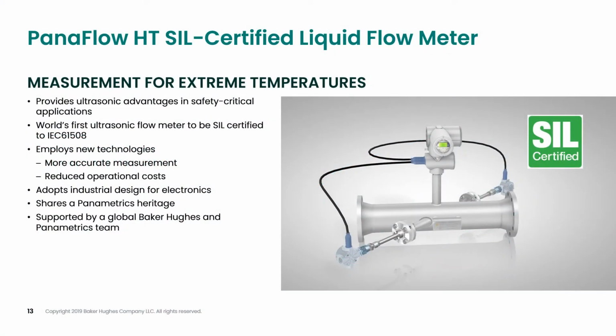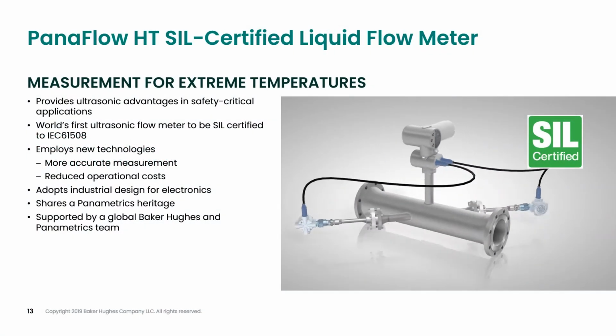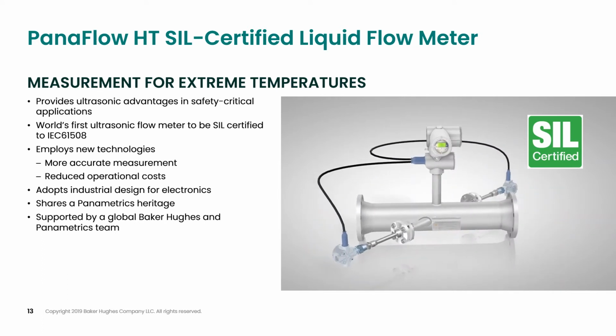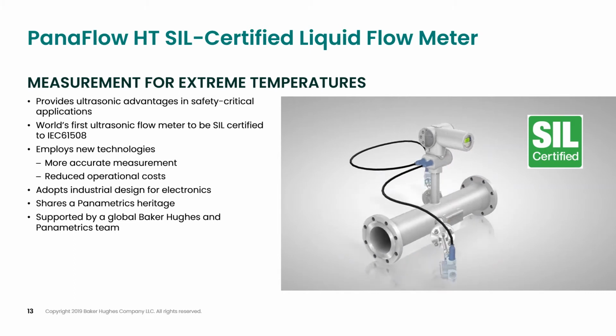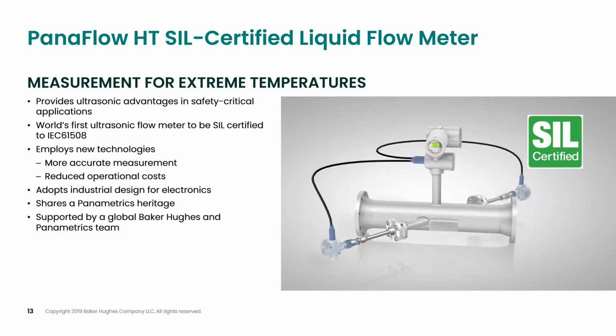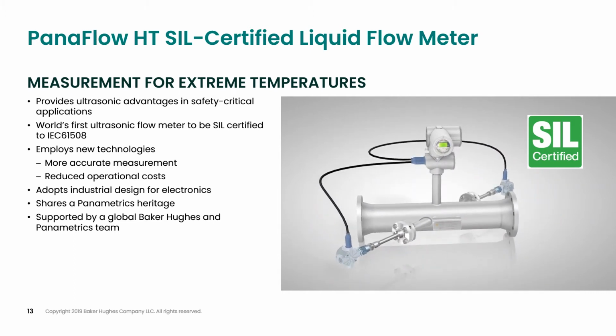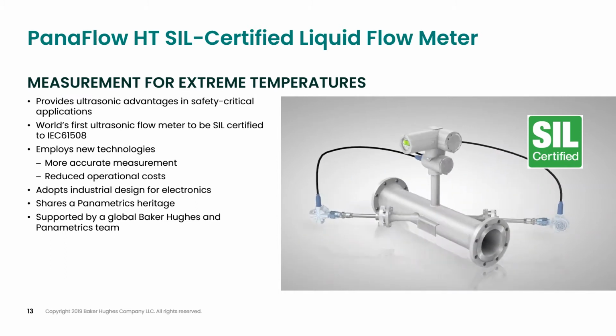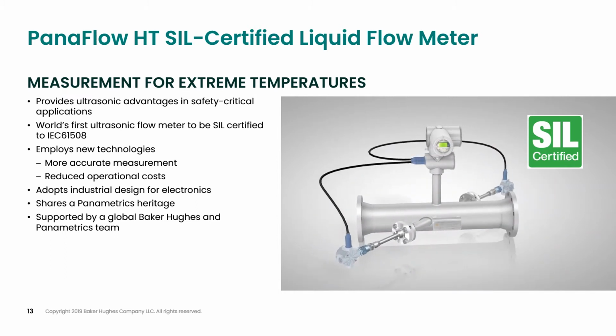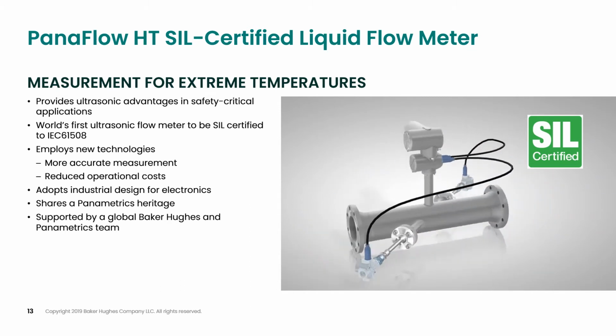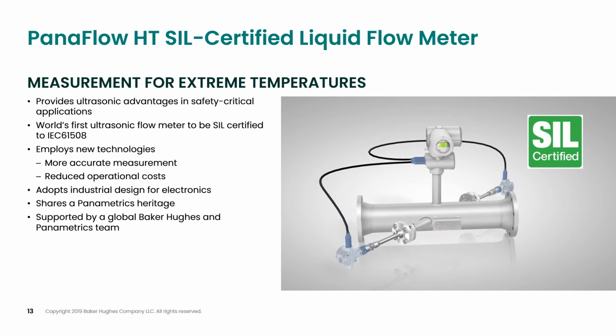PanaFlow HT is our solution for extreme temperature application. It provides flow measurements for either process control or safety critical applications. PanaFlow HT was the world's first ultrasonic flow meter to be SIL certified. The PanaFlow HT improved on our current design with bundled wave technology to provide a better overall flow measurement based on the Panametrics heritage. This meter is also supported by the global Baker Hughes and Panametrics service and support team.